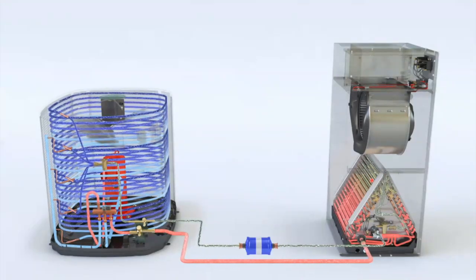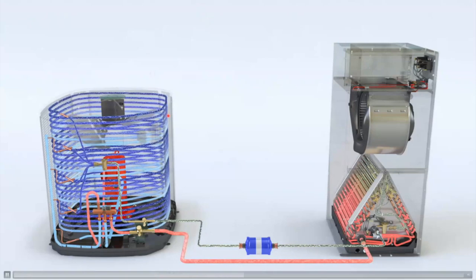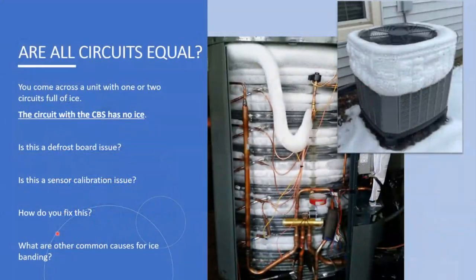So when you have a heat pump outdoor coil, you do have essentially more than one coil to make up the coil. So in this case, you can see 4 coil circuits. It's like 4 separate coils to make one coil. So coming out of the TX valve, we've got our distributor, comes out to 4 different coils. And then we have a header at the end of them to tie them all together. Now, most outdoor coils you're going to see have about 6 circuits, and not all circuits will be the same.